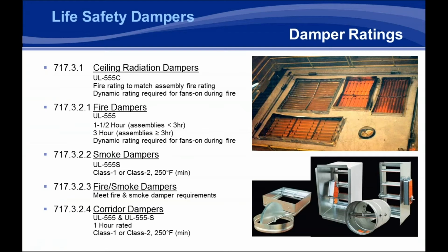Now, there are some new things to the code. Most of these dampers that we list here have been in the code, but there have been some minor changes to the ceiling radiation dampers and the corridor dampers that I'd like to touch on for the 2015 version of the code. The ceiling radiation damper changes basically stem from part of the requirement from the Uniform Mechanical Code.